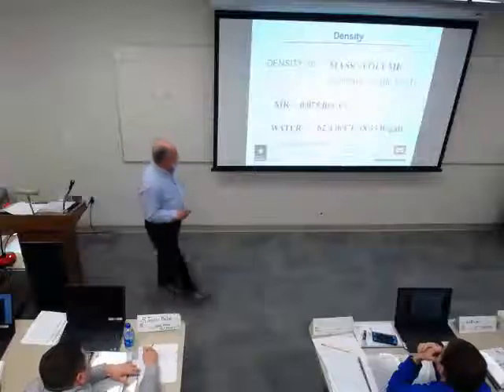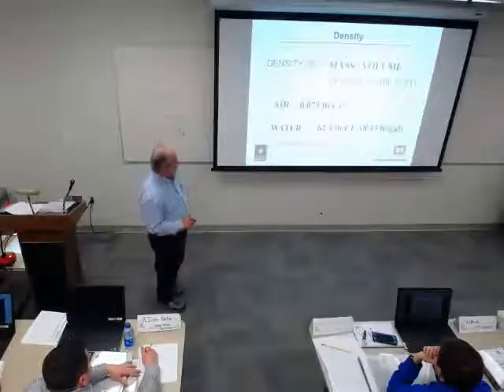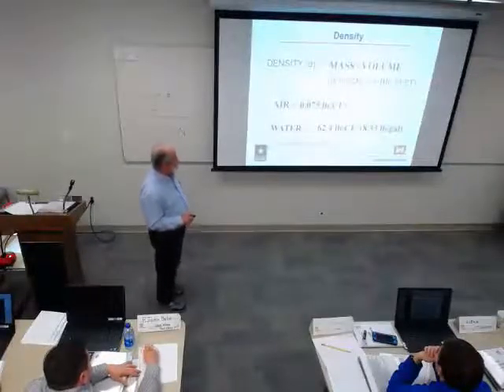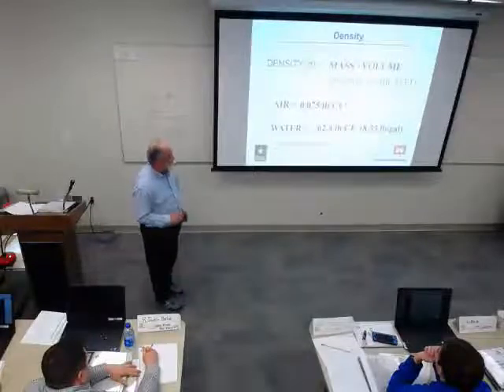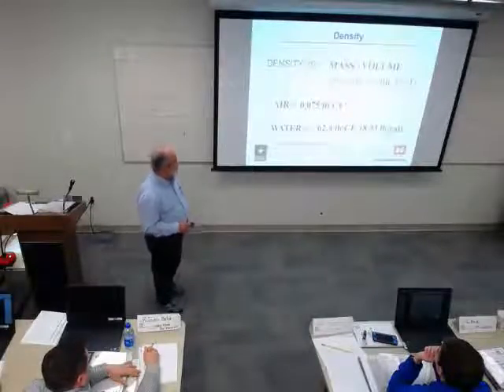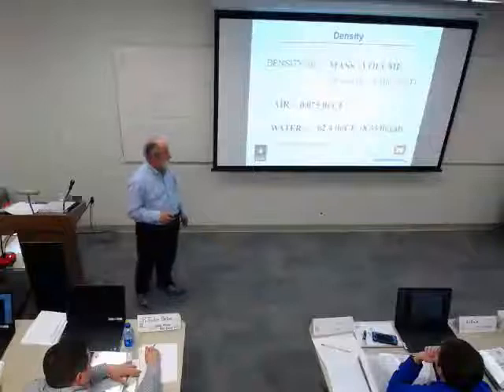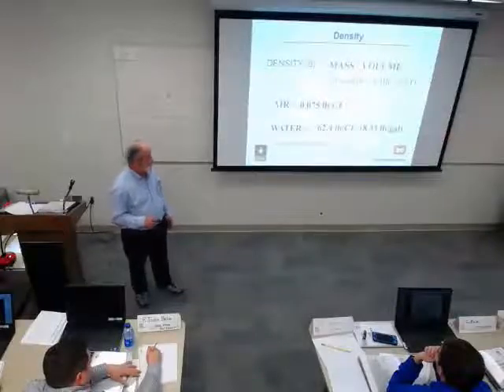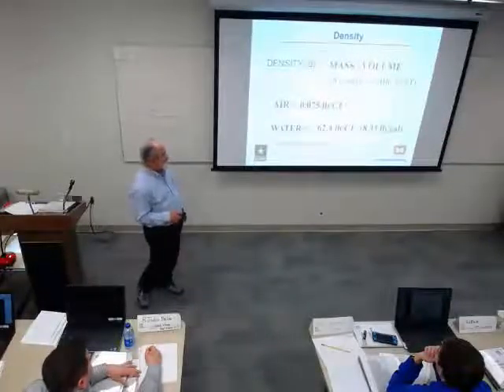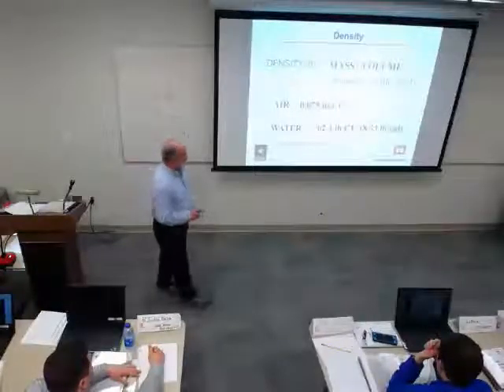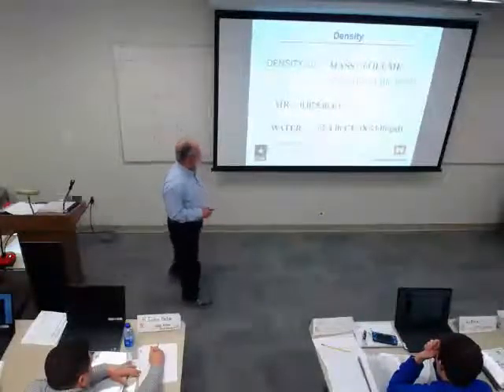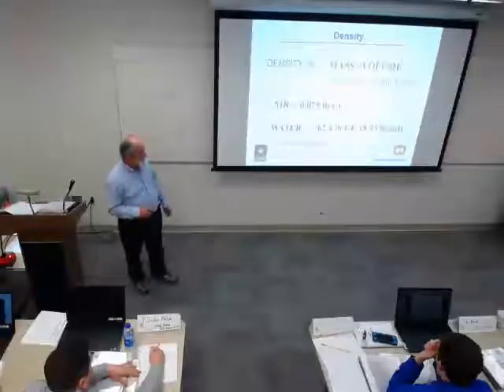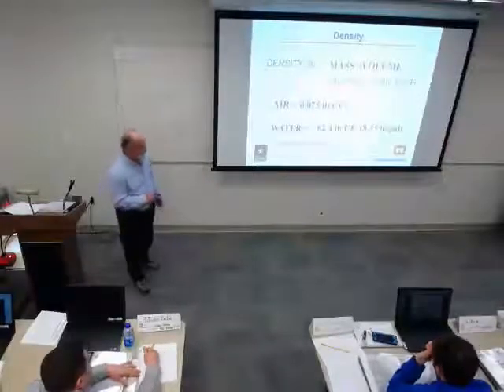Density is mass per volume, in pounds per cubic foot. For air at standard conditions, it's 0.075 pounds per cubic foot. Water is 62.4, and that's 8.33 pounds per gallon. I just mentioned water at 62.4, I believe that's at about 42 degrees.